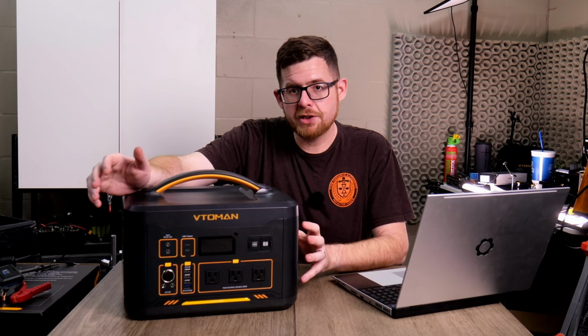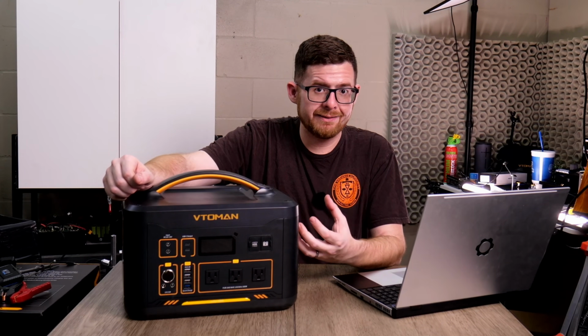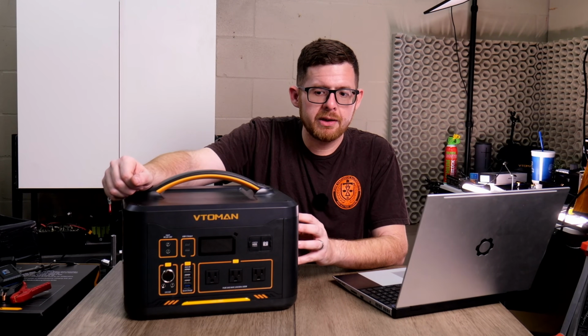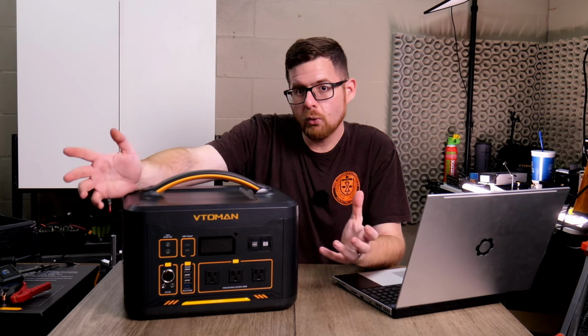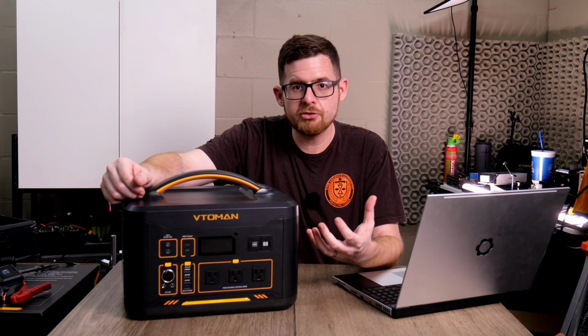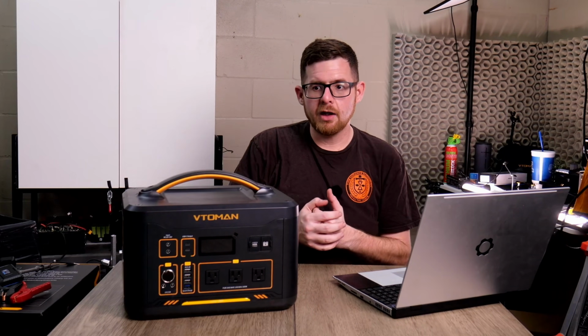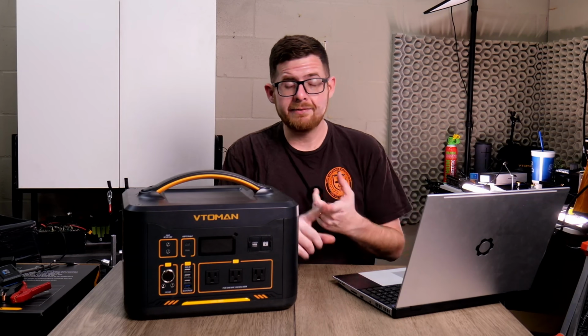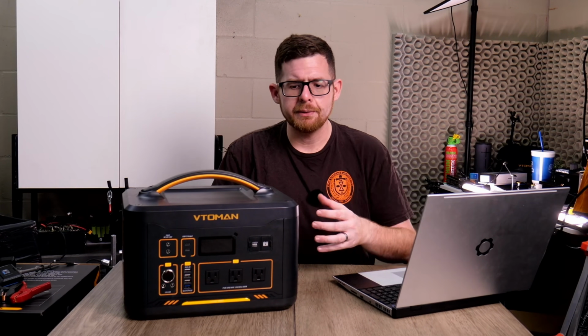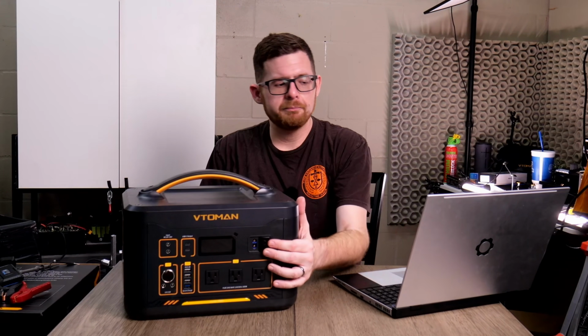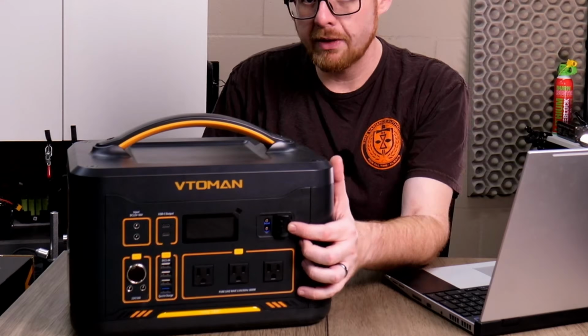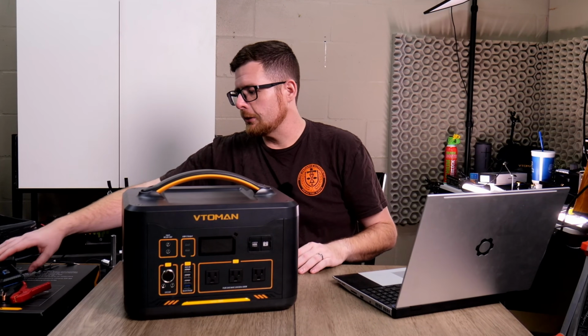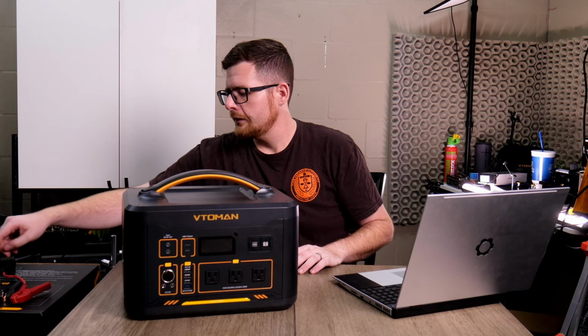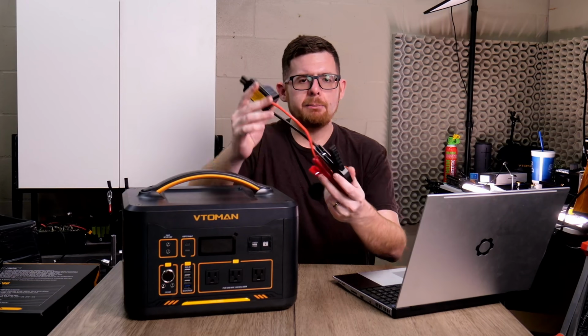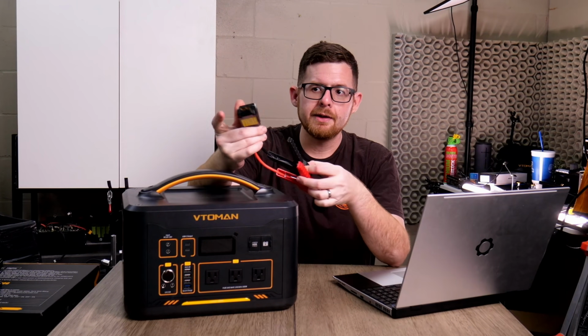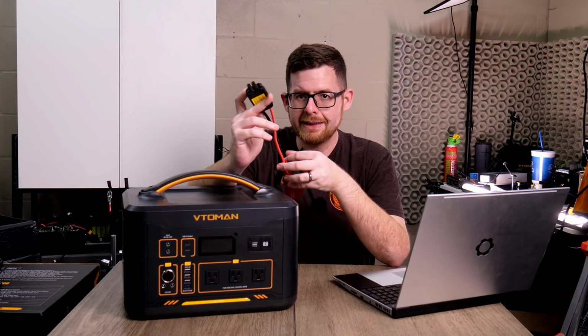On top of all the issues I found inside the unit, one issue I found right in the box. This is called the Jump 1800 for a reason - it's meant to have jump starter functionality that, based on claims I saw, could jump start up to a 7-liter diesel or a 9-liter gasoline engine off just this port up front. I took a look at this port and saw something familiar - it looked very similar to a standard called EC5, which you generally see on jumper cable boxes like this. The port here, though, is unfortunately just a little bit different.